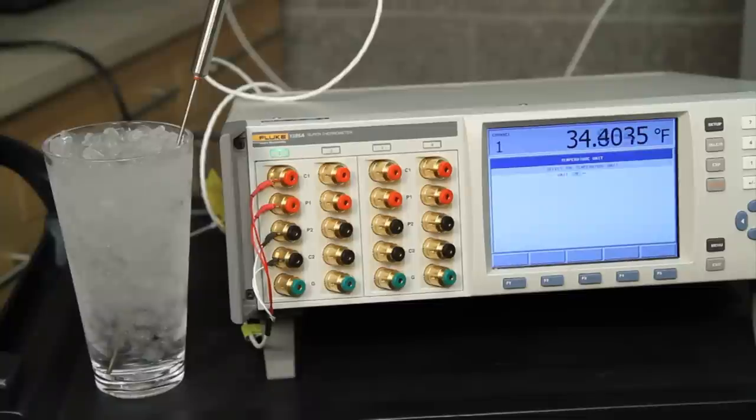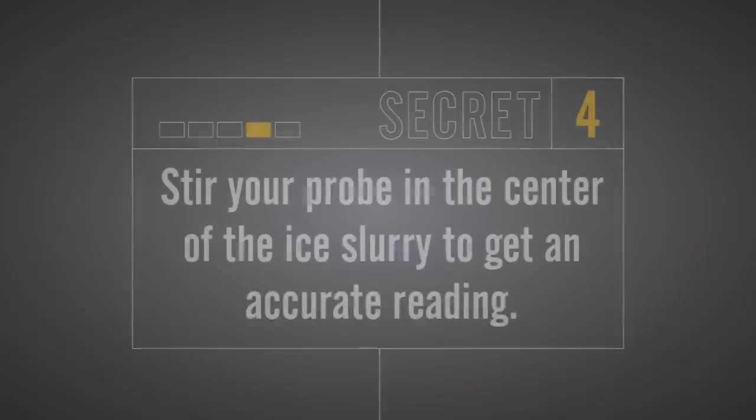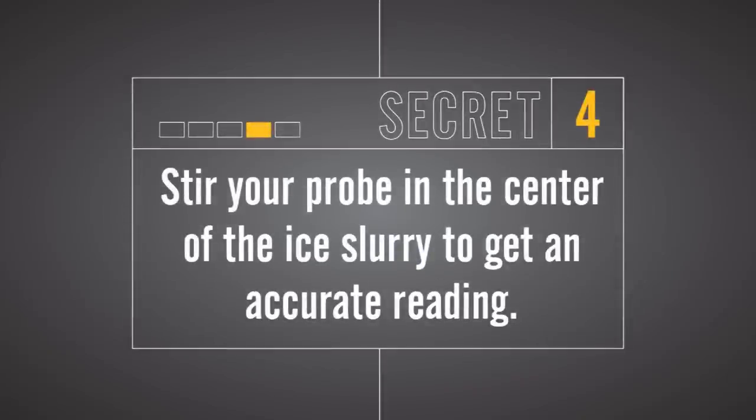That's also why one of the cardinal rules of ice baths is to keep your probe sensor up off the bottom of the glass. Secret number four: stir your probe in the center of the ice slurry to get an accurate reading.